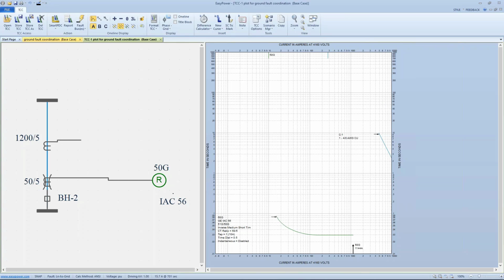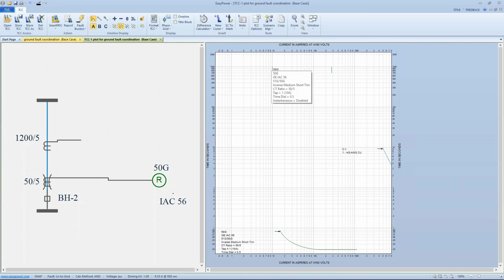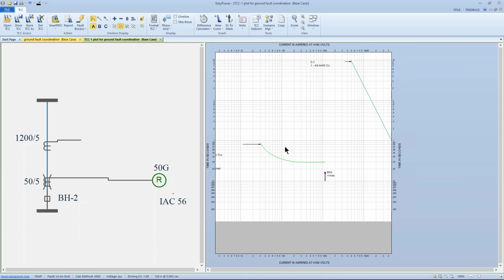So what we've done is set up the pickup point, this tick mark up at the top of the screen. And you can see we've set it up here for 10 amps, or a 10 amp range, and then it's scaled based upon where we set that tap. So if we set it higher, meaning we'll tolerate current at a higher level, at this point I've got it set to 20 amps, and then the time dial determines how long we're going to tolerate that particular level of ground current.